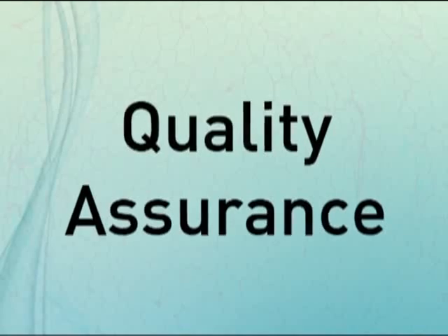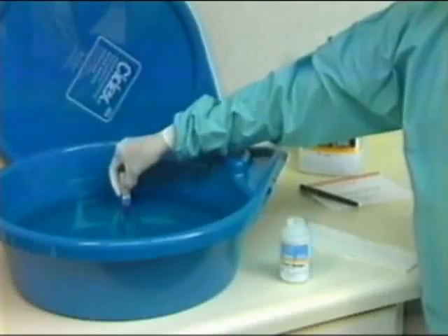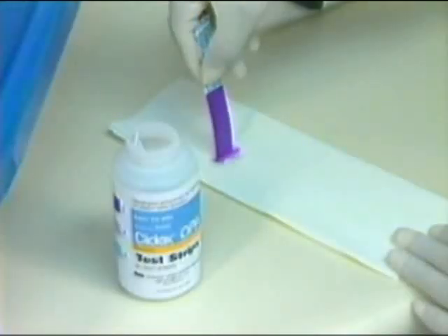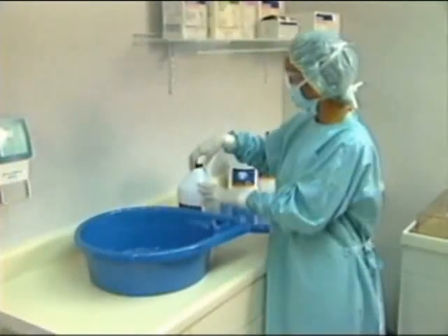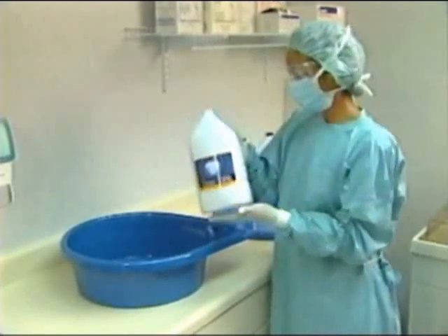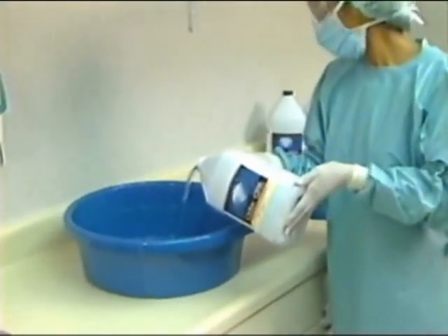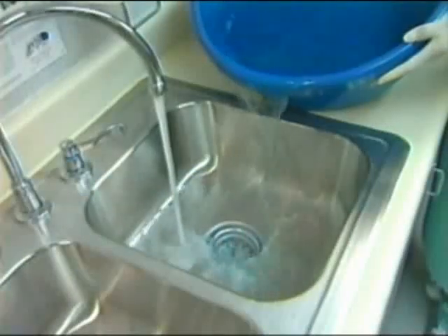Quality can be assured by the proper use of Cidex OPA solution test strips. The solution must be tested using the test strips to verify that the minimum effective concentration is still present. Once Cidex OPA solution has reached either the end of its 14-day reuse life or the minimum effective concentration (MEC), the solution can be discarded down drains in accordance with local and state regulations.